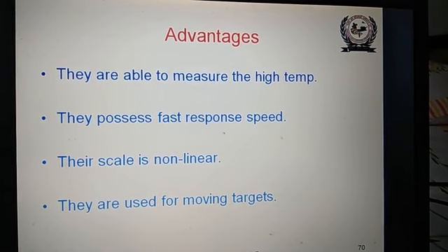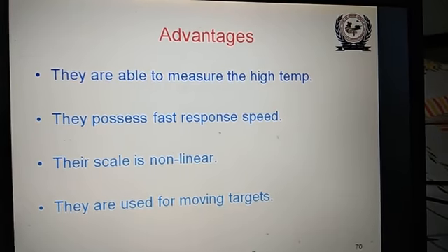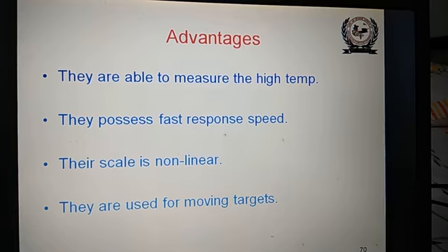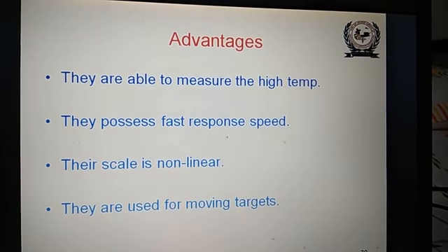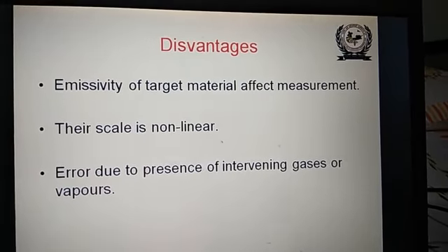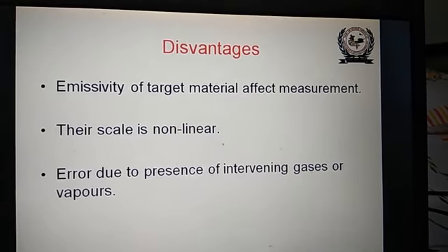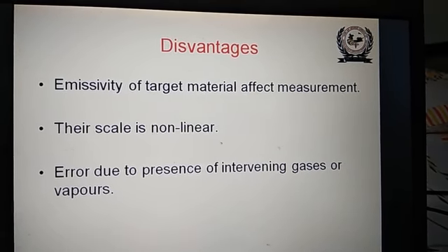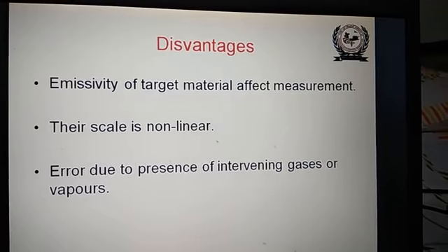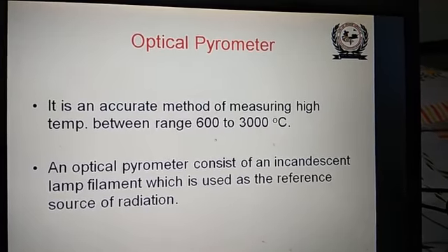Its advantages: they are able to measure high temperatures. They possess fast response speed. Their scale is non-linear. They are used for moving targets. Disadvantages: emissivity of target material affects measurement. Their scale is non-linear. Error due to presence of intervening gases or vapors.